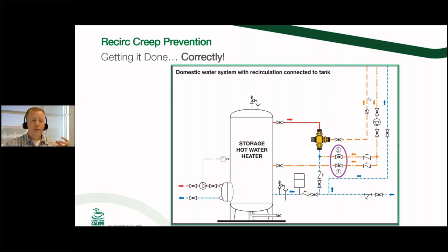Okay, so this is how you would do it though. This is a really interesting scenario where this is how you can fix recirc creep by basically, again, overriding the mixing valve, because per ASSE 1017, they're not required to have those mixing, and this isn't just our mixing valves. I'm going to say this is everybody's mixing valves, but per ASSE 1017, it's not a requirement to be able to completely shut off that hot inlet. Okay, so we call this out instead of an aquastat in order to maintain that loop temperature without creating recirc creep and things like that. So again, really interesting scenario, but hopefully you guys can latch onto that one.